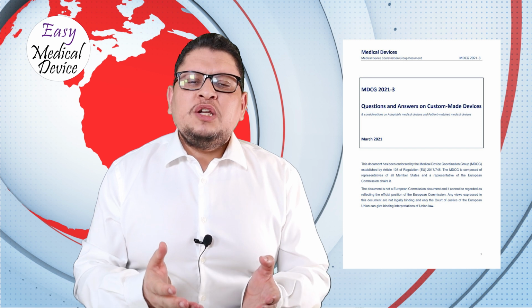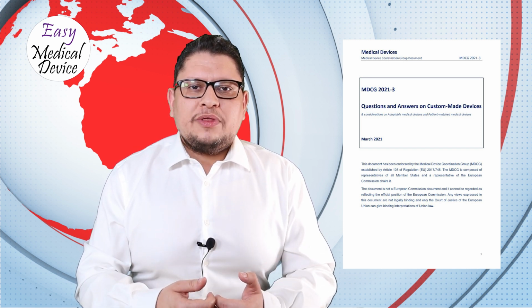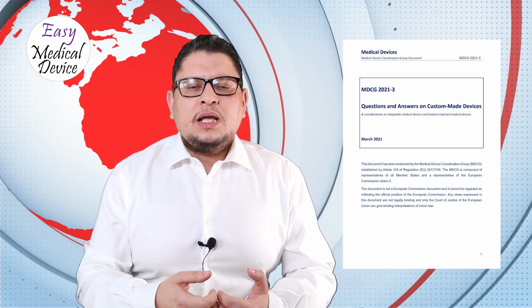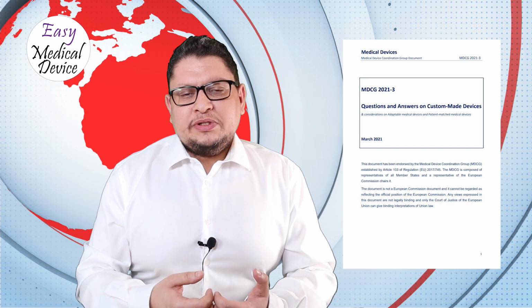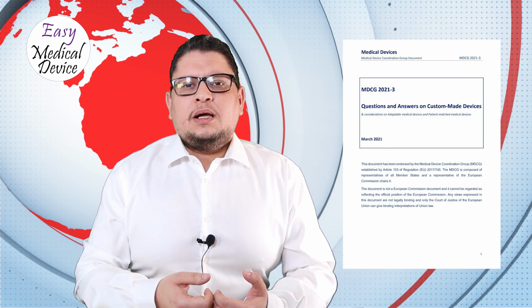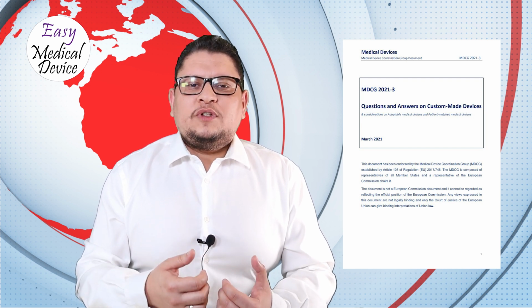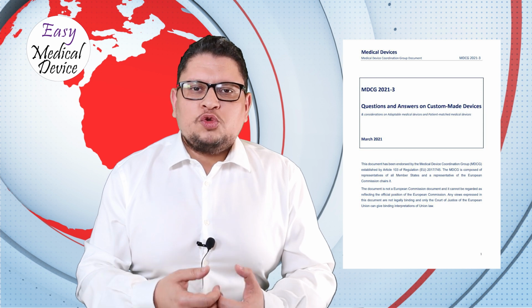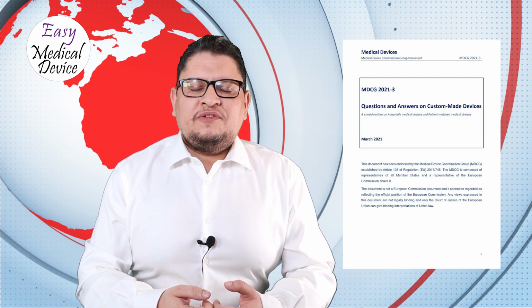So if you are manufacturing those kinds of devices, and maybe you are not aware now that you need a notified body, it's important that you move forward quickly, because notified bodies are really busy. If you can get a date now for your audit, it will help you a lot. But if you have custom-made class 2A or class 2B devices, you don't need that. You still need the same process as before, but following now the EU MDR requirements.